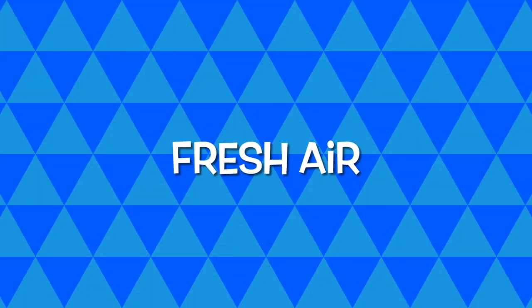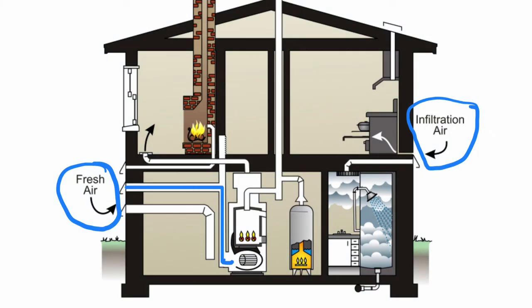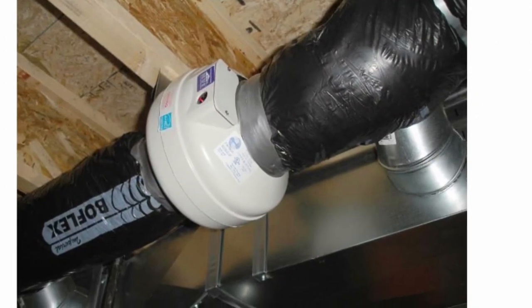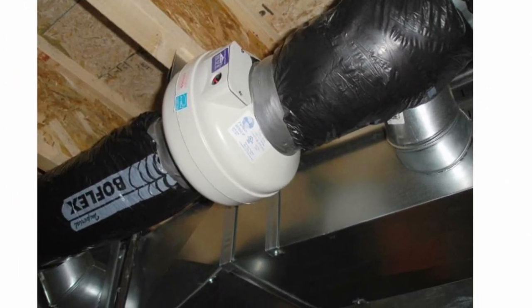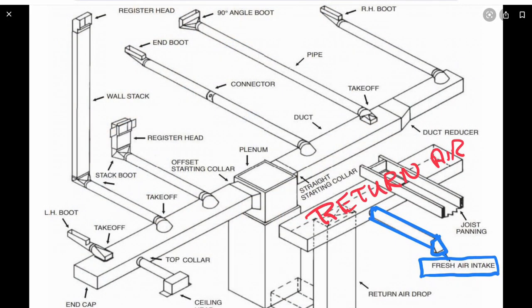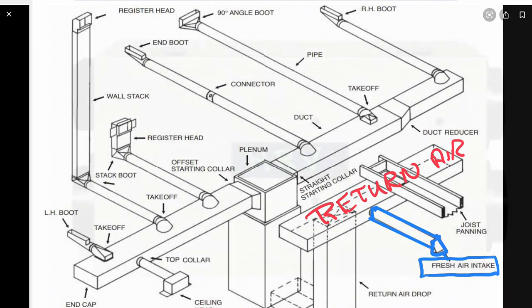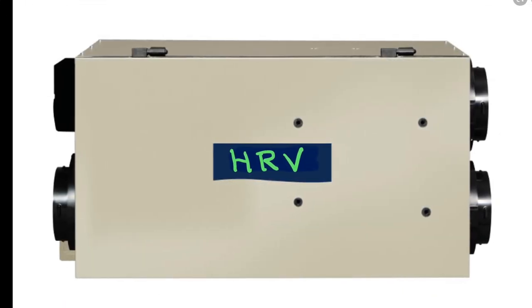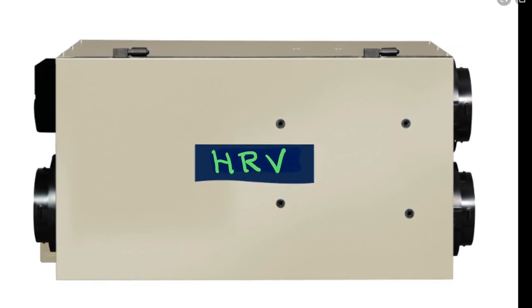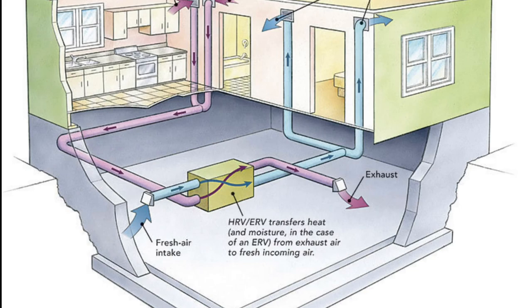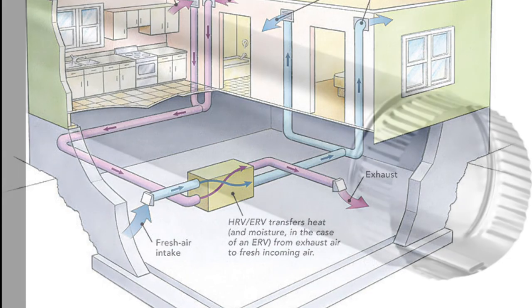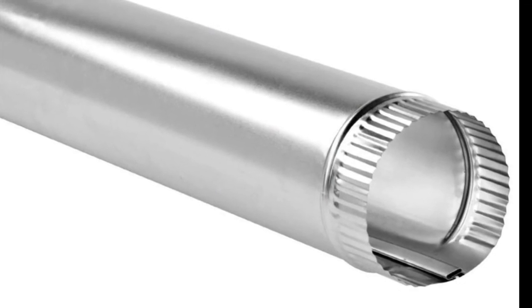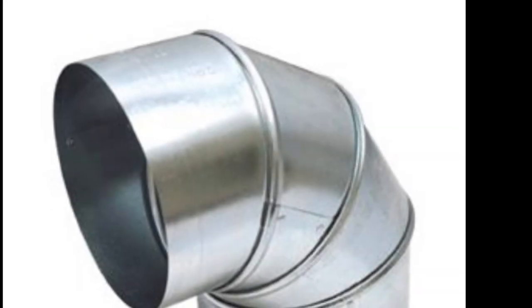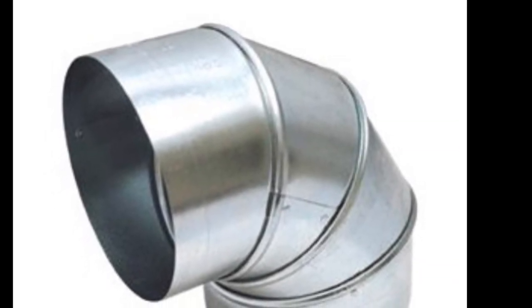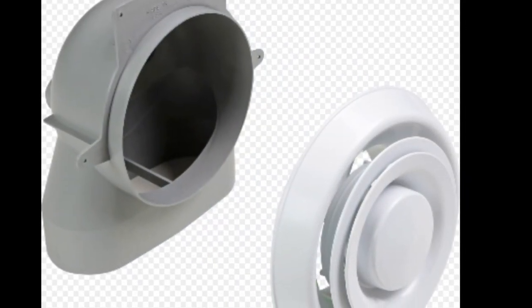The opposite of exhaust or stale air is fresh air or outdoor air. This is also brought in by fans. It can either be an inline fan, or it can even come in through our return air duct with a simple duct going outside and its hood. But the most popular way of bringing it in is through our HRVs, heat recovery ventilators. After the ventilator, it's still installed with, most of the time, round pipe and round elbows, and it will finish off, again, either in the ceiling or on the wall, using a stack head and diffuser.